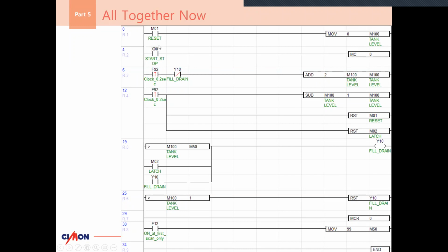If I want to start and stop my draining and filling, I activate X00, and this will activate that MC command we were talking about. MC0 is looking for MCR0. If I come down here, I see MCR0. So all of this logic in the middle will not activate until this bit has been activated itself - it's a master control run.